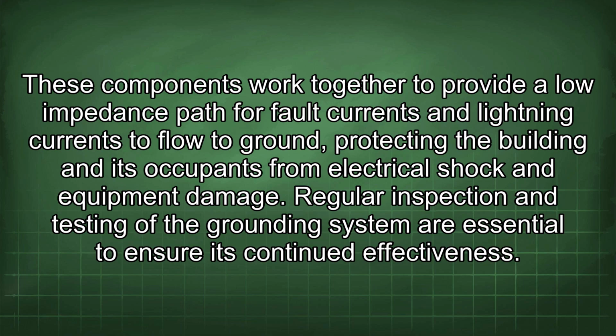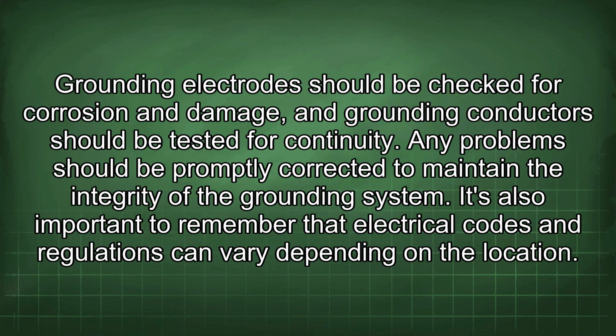Regular inspection and testing of the grounding system are essential to ensure its continued effectiveness. Grounding electrodes should be checked for corrosion and damage, and grounding conductors should be tested for continuity. Any problems should be promptly corrected to maintain the integrity of the grounding system.